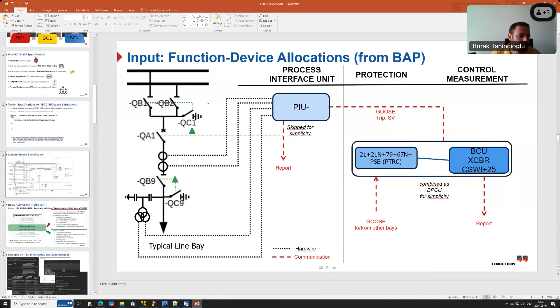But I will go through quickly all the tasks. Basically it's the combination of tasks we want to do for specifying system engineering of the substation. So, configuring the buses, data sets, if there is functional naming, instantiate the logical nodes with prefixes and suffixes, subscribe to goose messages or maybe sampled values if possible. Add one client, which is the gateway that we will use, also the project, and also reserve the report for this specific client. At the end I will also explain why we need to instantiate the logical nodes to functions again.